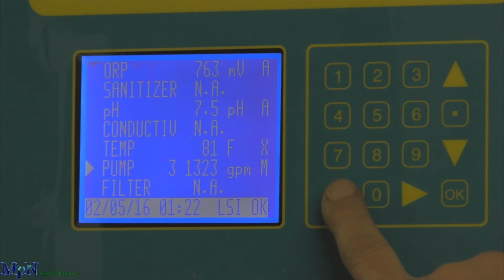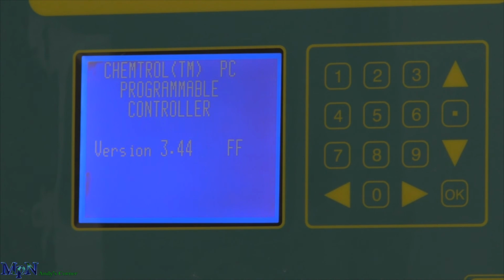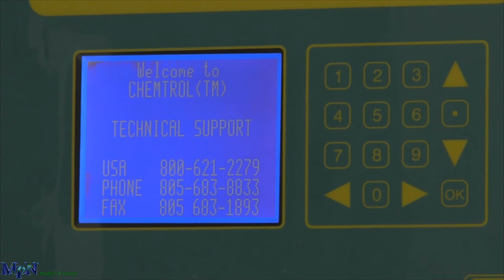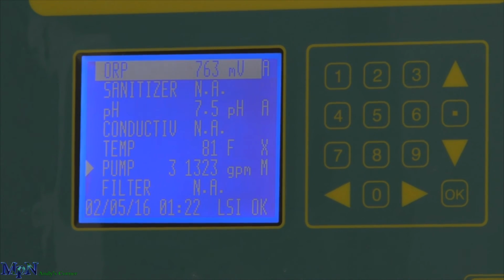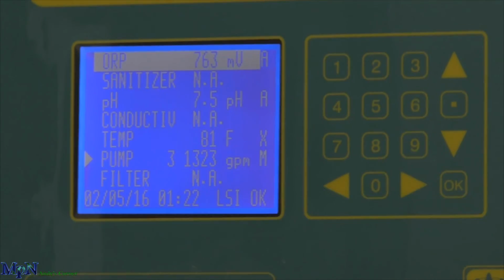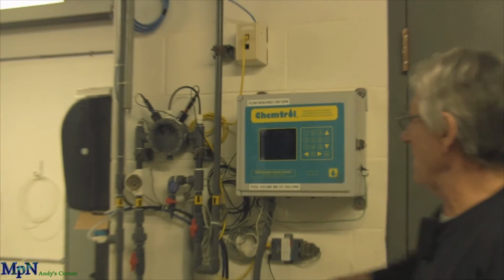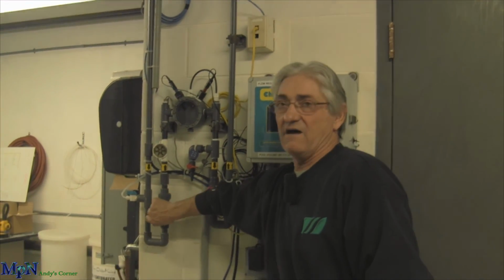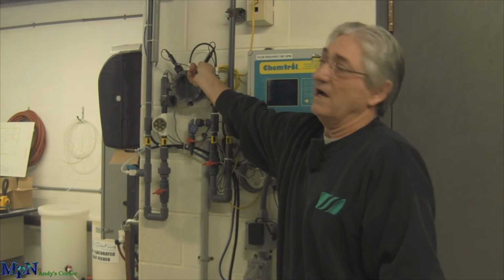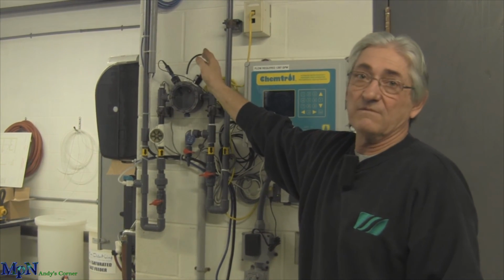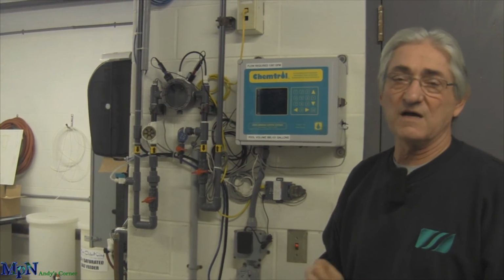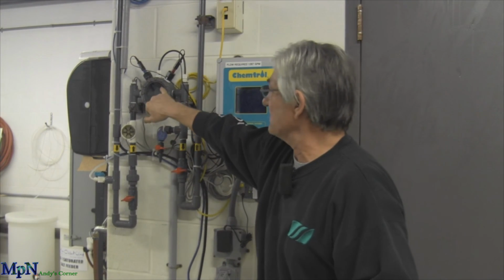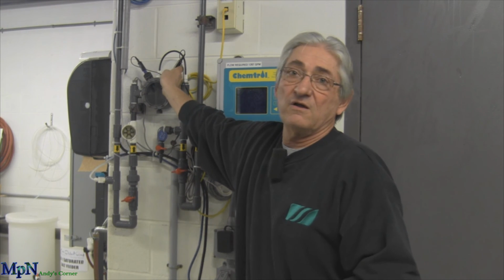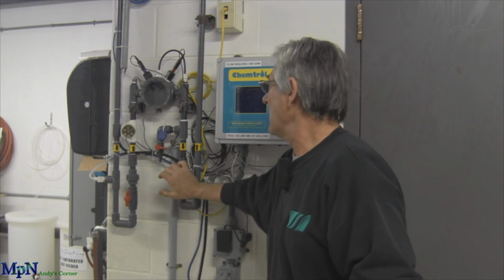Go back to the main screen and we'll be back on our home screen. The only normal maintenance we'd have is cleaning of the probes. To clean the probe, you would shut the controller off and shut your lines off going in and out of it. Unthread the jam nuts, pull the probes out, and rinse them off, using soap and water, maybe a toothbrush with soap and water on it, to clean just the glass bulb. Slide them back in, tighten the jam nuts, and then turn the flow back on.